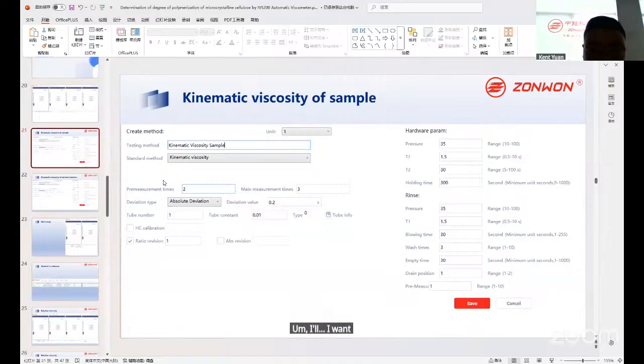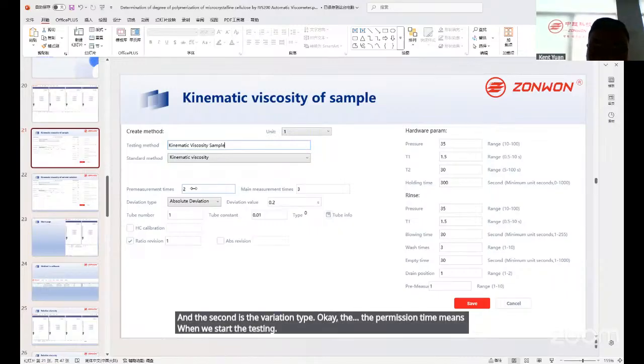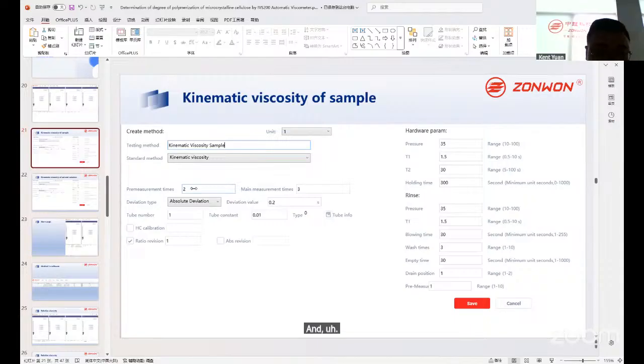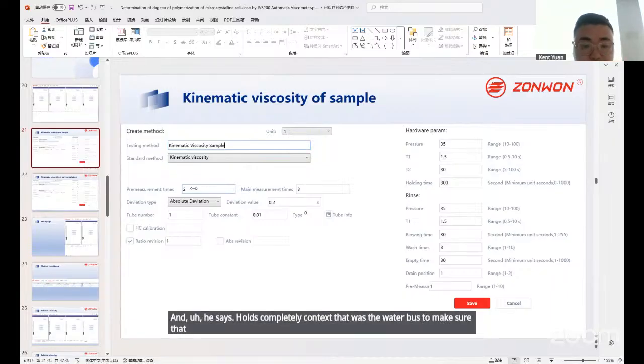I want to introduce two parts. First is the pre-measurement times and main measurement times. And the second is deviation type. The pre-measurement time means that when we start the testing, the machine will test the sample automatically 2 times, and each time it will not record the flowing time. By doing this, we make sure the sample goes through the tube and is in complete contact with the water bath, so that the temperature of the sample is 100% the same as the water bath.